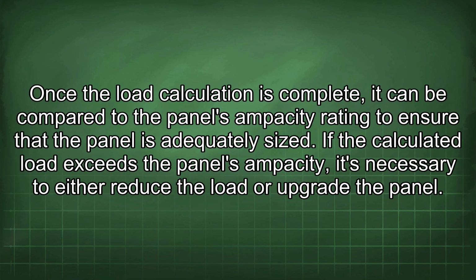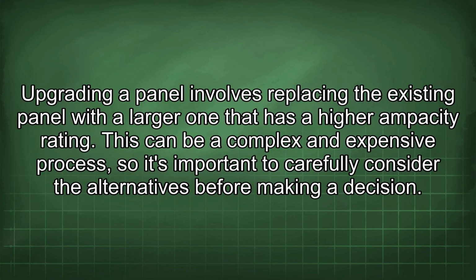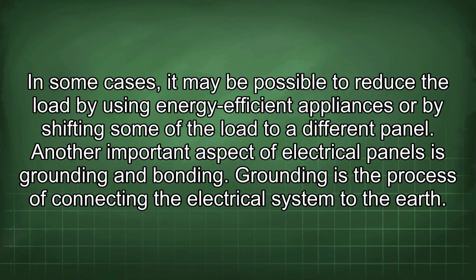Once the load calculation is complete, it can be compared to the panel's ampacity rating to ensure that the panel is adequately sized. If the calculated load exceeds the panel's ampacity, it's necessary to either reduce the load or upgrade the panel. Upgrading a panel involves replacing the existing panel with a larger one that has a higher ampacity rating. This can be a complex and expensive process, so it's important to carefully consider the alternatives before making a decision. In some cases, it may be possible to reduce the load by using energy-efficient appliances or by shifting some of the load to a different panel.